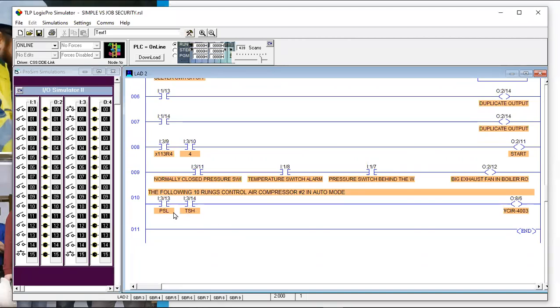What's probably most important is matching the schematic. Many times the tags in the program will match a schematic — it starts with a P&ID (piping and instrumentation diagram) in the design phase. On that P&ID they might call it 'pressure switch low dash one' or 'unit 32 PSL' — since they're standard, they're understandable to most people. It starts on the P&ID, then makes its way to the schematics which say the exact same thing. Matching the schematic is important because when you're troubleshooting, that's what you're looking at.